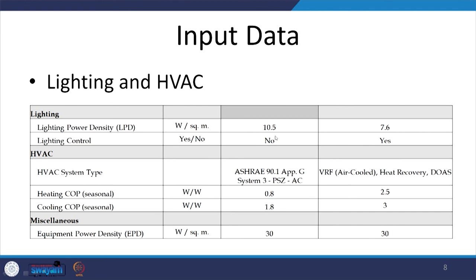For lighting and HVAC: initially we considered a lighting power density of 10.5 W/m², but here we will reduce it to 7.6 W/m². In the base case there were no lighting controls used, while in the proposed case we will be using lighting controls. For HVAC, in the base case we used System 3 as per ASHRAE 90.1 Appendix G, while in the proposed case we will use Variable Refrigerant Flow (VRF) along with heat recovery.